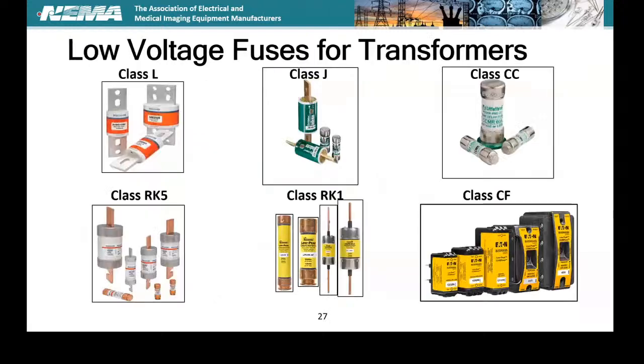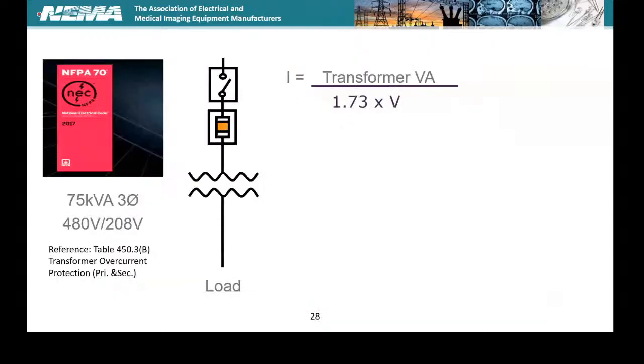And these are your options: the L's, the J's, RKs, the RK1, and then you got the class CC fuse and the CF fuses. So we go to the application here. We've got a 480 volt, 208 volt step down transformer. We've got some overcurrent protection. We've got some cases where we can just protect the primary, or we can protect the primary and secondary. They both meet certain conditions. So we'll go through some examples.